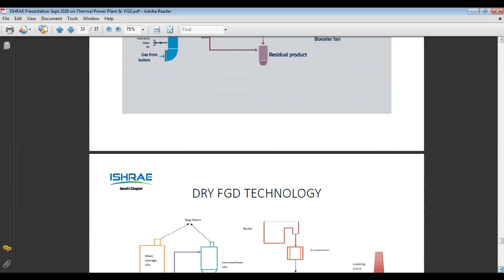And now this is the dry FGD technology. In dry FGD technology, the reaction takes place in dry mode, as we are going to install in most of the existing power stations in India. This technology can be installed in the boiler or in the duct, but in the existing boiler it is not recommended to install because it affects the boiler efficiency. So it is recommended to install in between the economizer and the air heater, or it can be installed in between the ESP and the air heater. That is basically its reactivity.